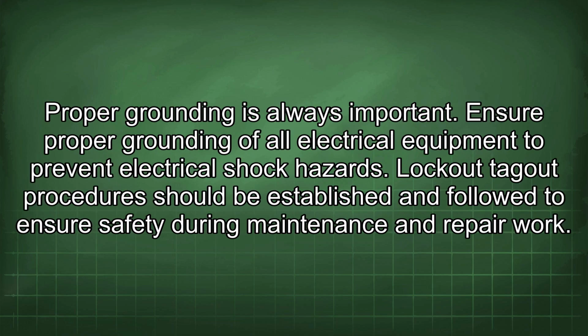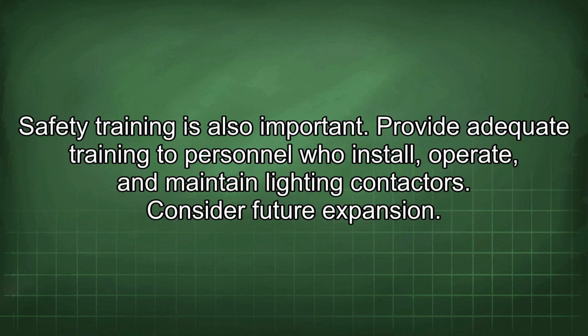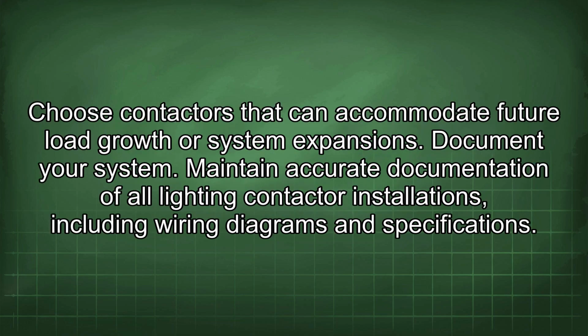Proper grounding is always important. Ensure proper grounding of all electrical equipment to prevent electrical shock hazards. Lockout-tagout procedures should be established and followed to ensure safety during maintenance and repair work. Safety training is also important. Provide adequate training to personnel who install, operate, and maintain lighting contactors. Consider future expansion. Choose contactors that can accommodate future load growth or system expansions. Document your system. Maintain accurate documentation of all lighting contactor installations, including wiring diagrams and specifications.